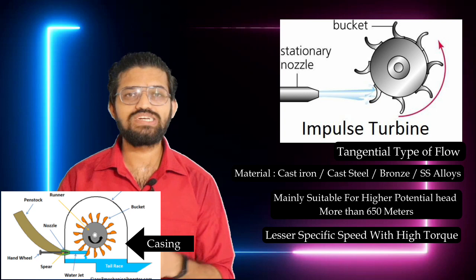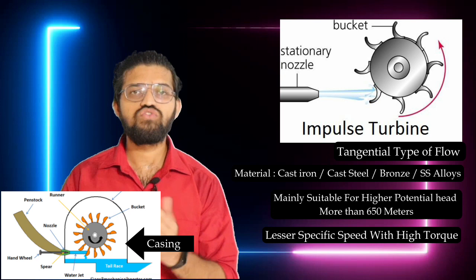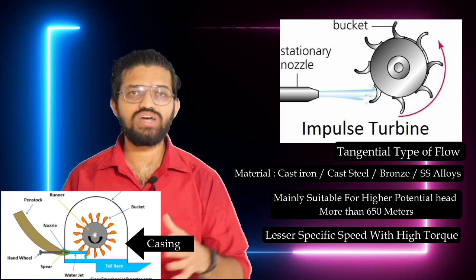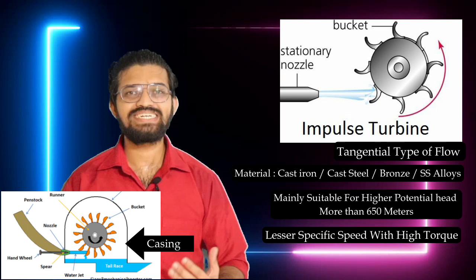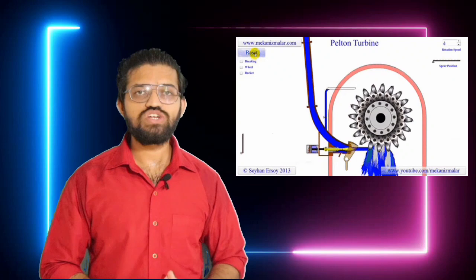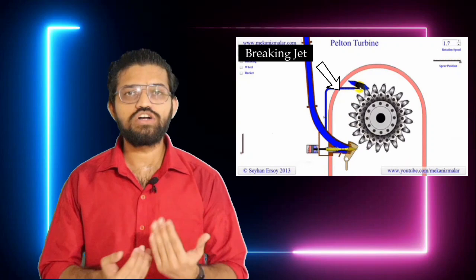A casing is provided around the turbine, made of materials similar to the turbine blades — cast iron, cast steel, or bronze. The main functions of the casing are to protect the Pelton wheel from the outer atmosphere, prevent water from dispersing outside, collect the water at the bottom in the tailrace, and act as a safeguard against accidents. When the Pelton wheel is rotating, a moment of inertia is induced, so even if the water supply is cut off, the wheel continues rotating.